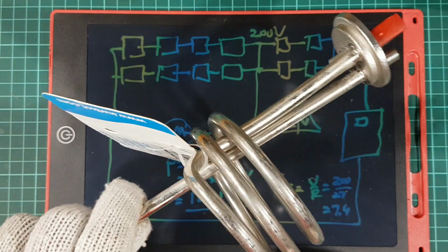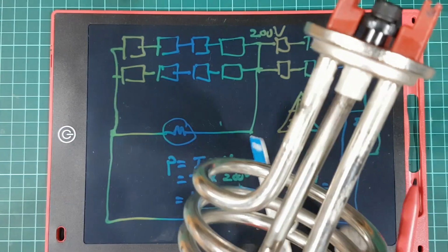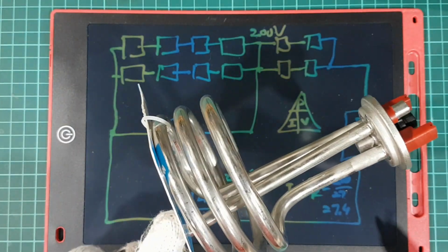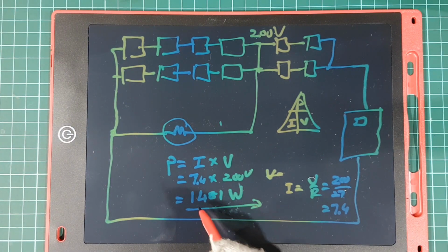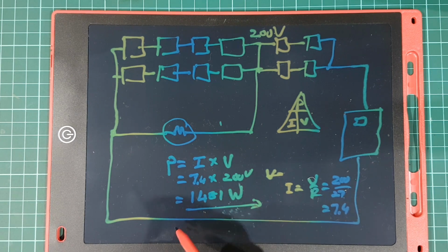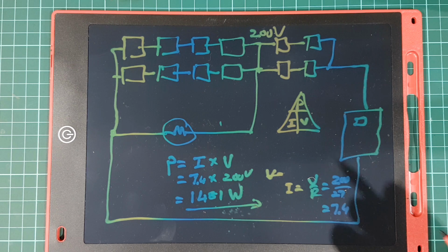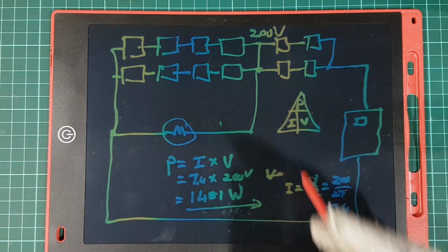So this is never pushed to full power, which means it most likely will last a lot longer than it would have lasted, as it's never pushed to its limits. It's literally idling. So our element would last longer. And the disadvantage is that if we would normally take 2 hours to heat up our water, in this case it would take maybe 2 3/4 hours or 3 hours. So that's the only disadvantage with the system. It might take a bit longer, but not a lot. And that's how simple it is to connect your geyser.